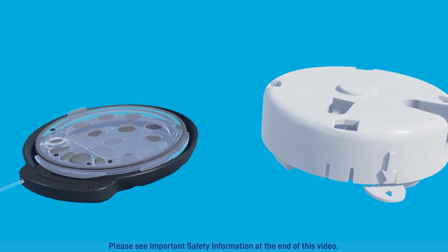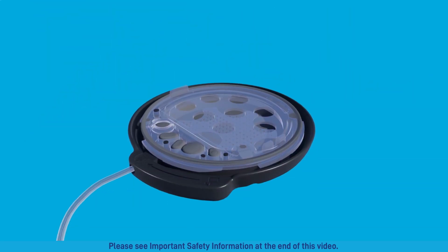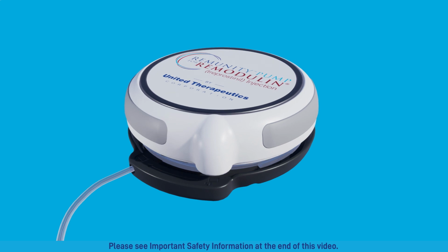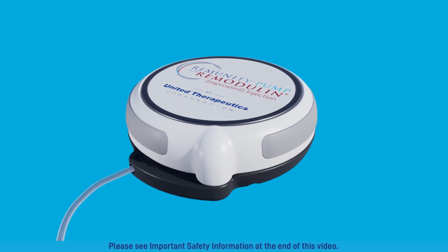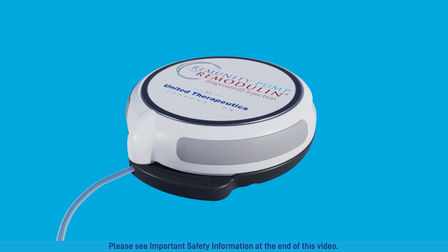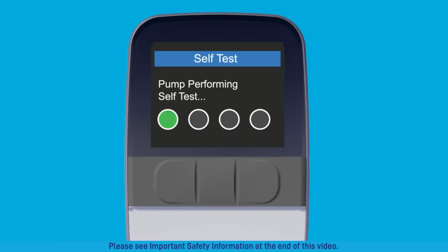Detach the white filling aid from the cassette and discard. Align the pump bump with the unlock symbol on the cassette. Push down and rotate clockwise until it is aligned with the infusion tubing and lock symbol. The pump will emit a series of beeps as it performs the self-test. It's important to wait until the self-test is complete to continue.